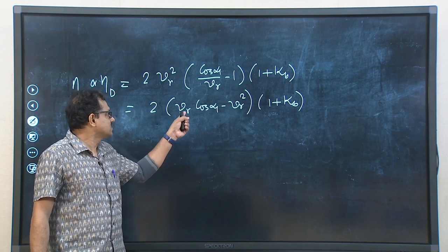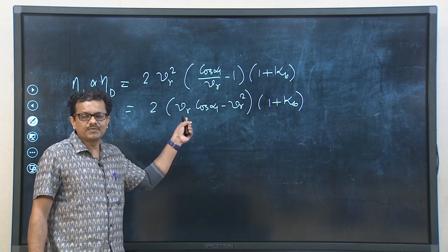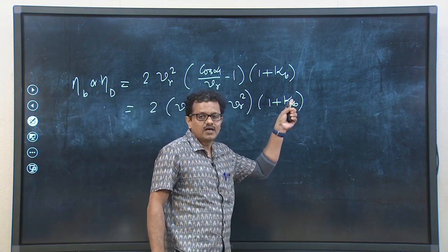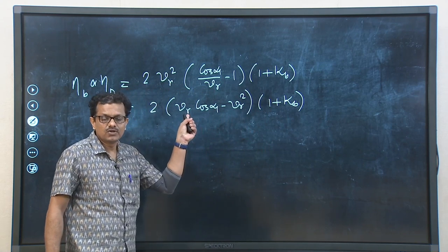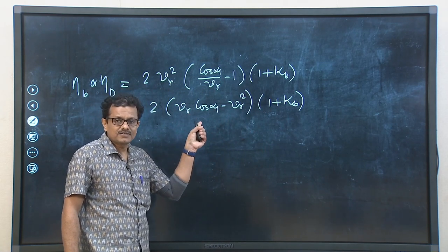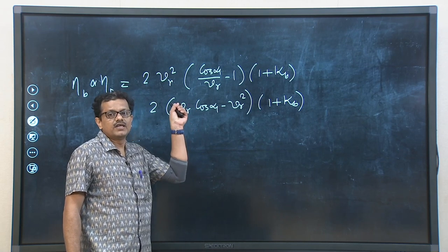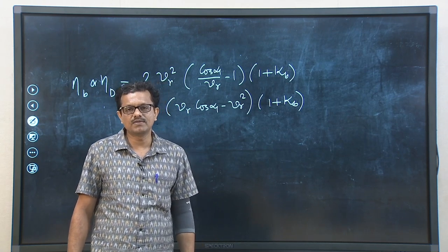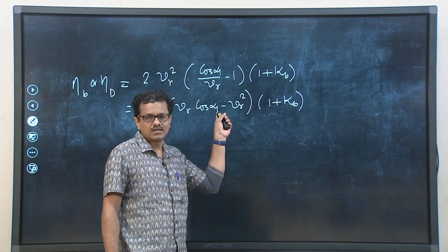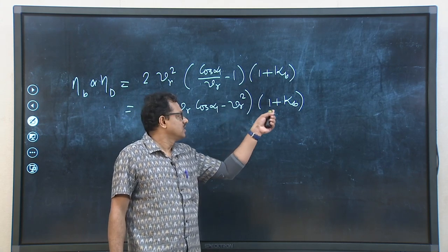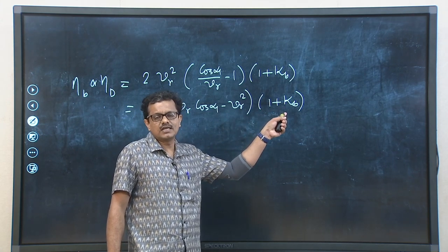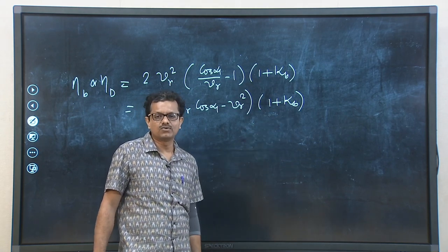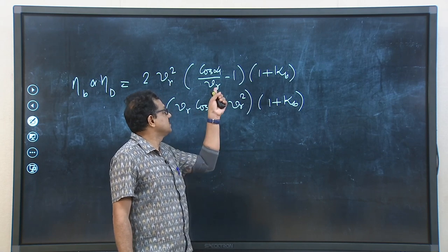Now, we can see that this blading efficiency or diagram efficiency is a function of flow angle, blade friction coefficient, and most importantly the velocity ratio. So, there must be an optimum value of Vr for which this diagram efficiency or blading efficiency should be maximum. Alpha 1 is fixed, because it depends on the designer. Kb is the blade friction coefficient, which cannot be equal to 1, but the ideal situation would be to maintain Kb equal to 1.